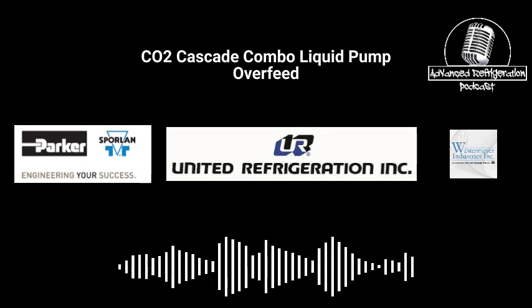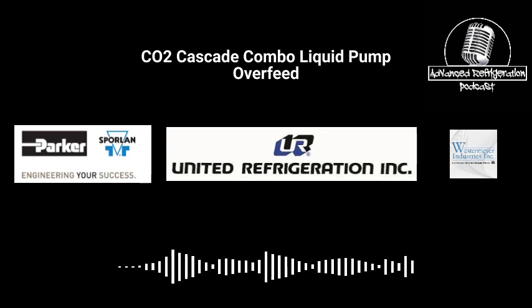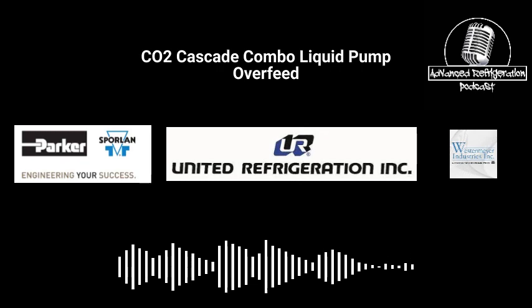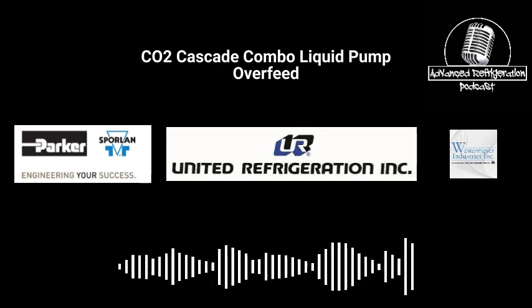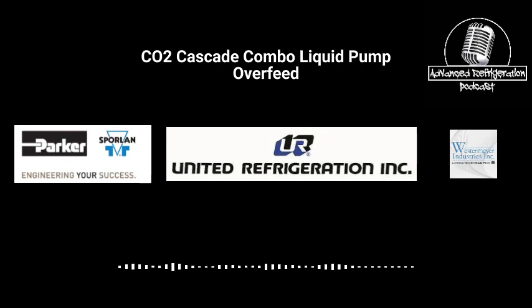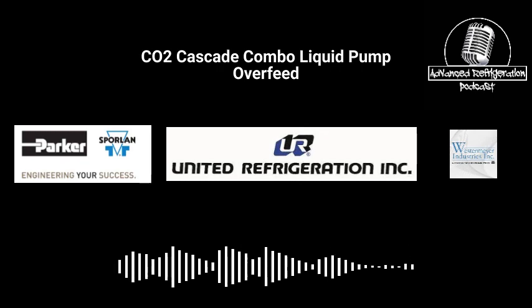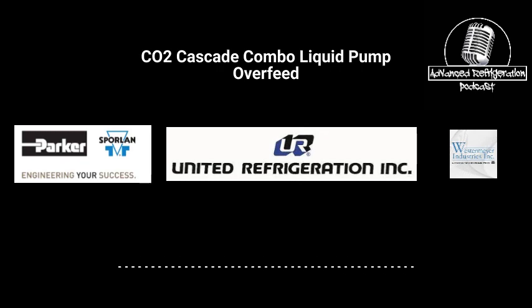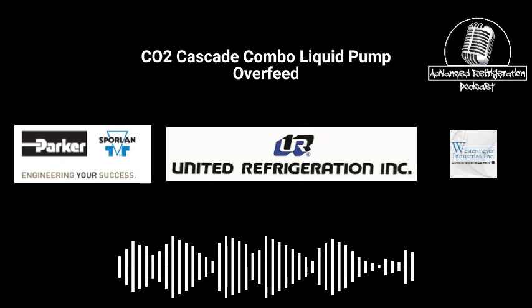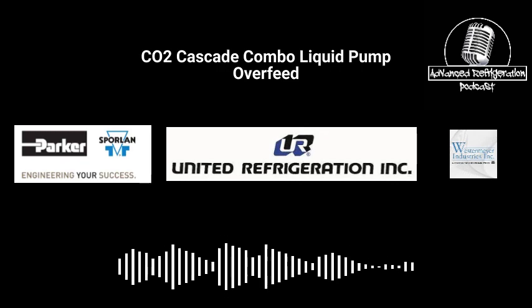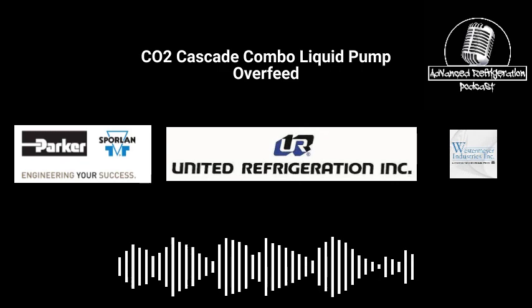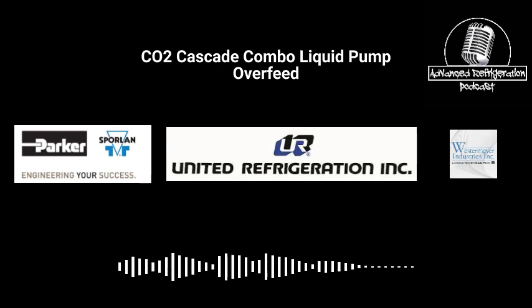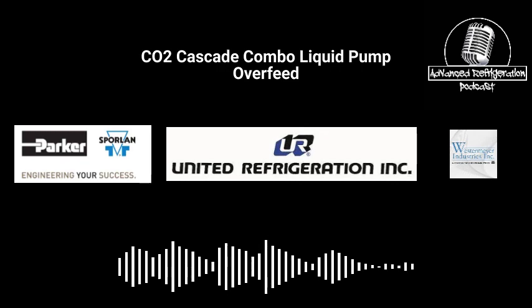So did he put it pointing towards the head then? No, towards the rear of the compressor, because the windings were getting the heat. Oh, okay. Yeah. So check this out too. If I blow up this picture, you'll actually see what I'm talking about here. Very cool. Because if you put it towards the windings, then it's going to cool the windings. Otherwise, it's going to go right towards the front. If it goes towards the front, it's not going to cool the windings and essentially cause that compressor to overheat.